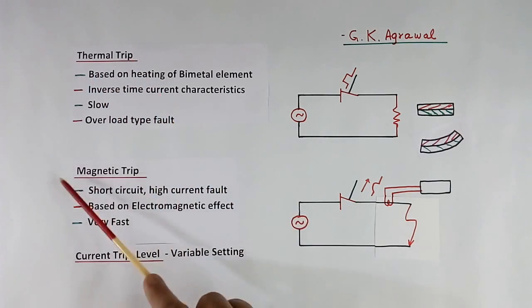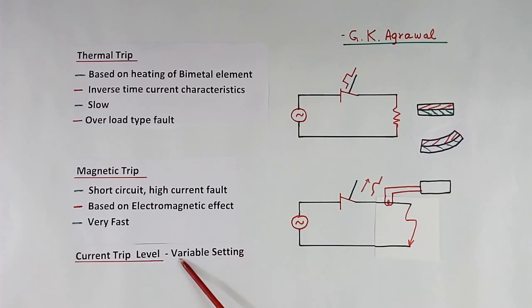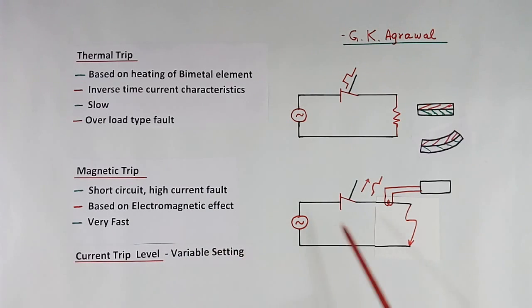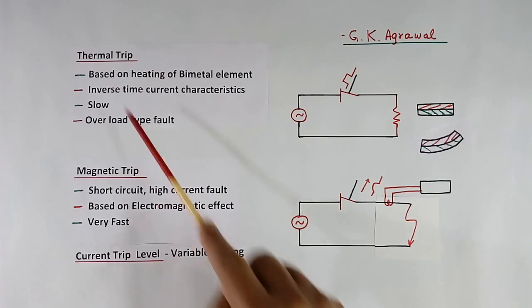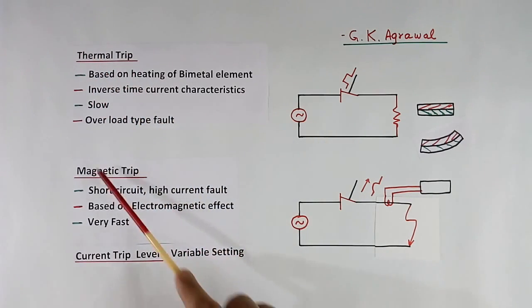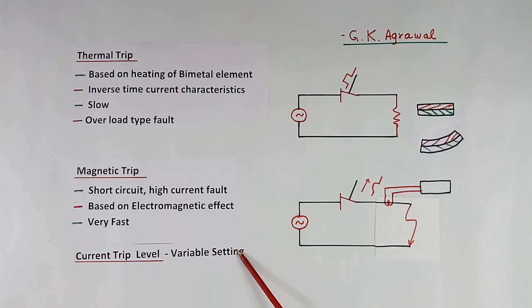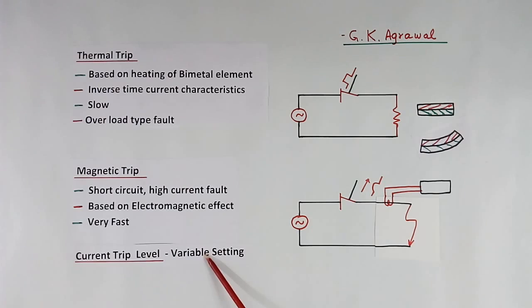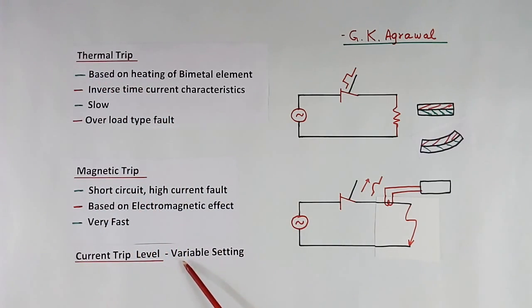For both thermal trip and magnetic trip, the current trip level will be variable in many cases. Some MCCBs will have only thermal trip variable setting, some will have only magnetic variable setting, or some will have both thermal and magnetic variable. So you can set the value to what you want.